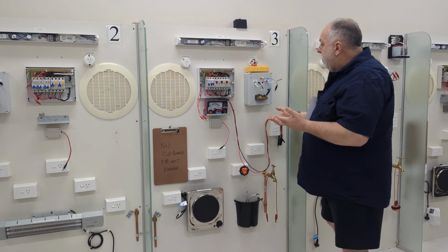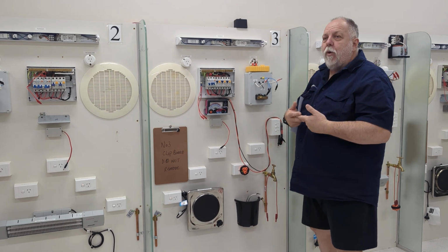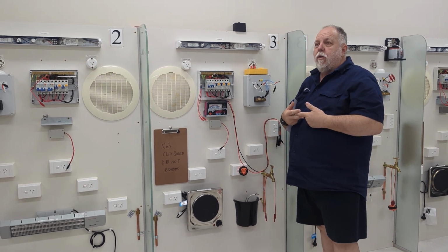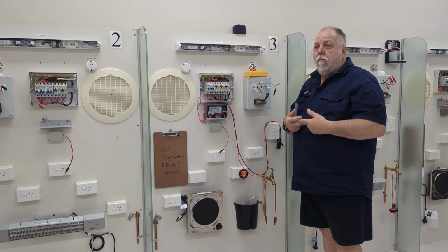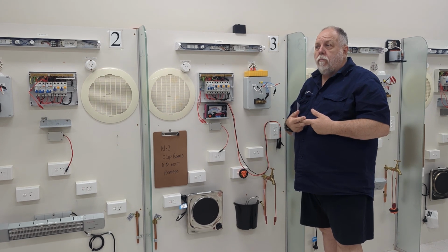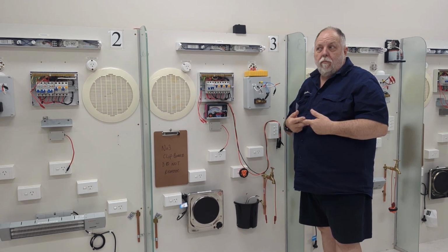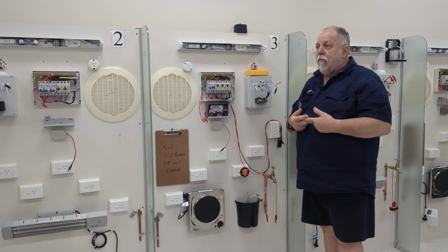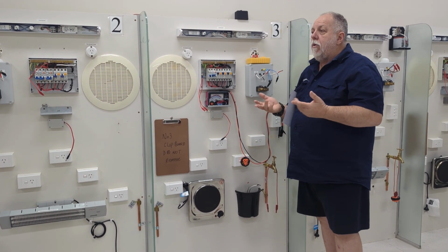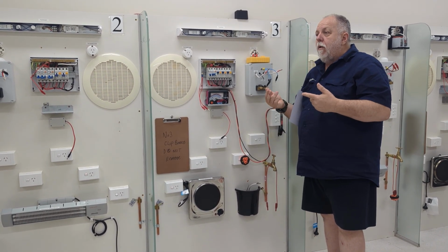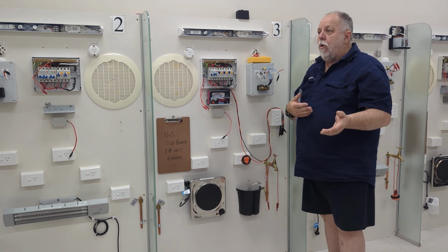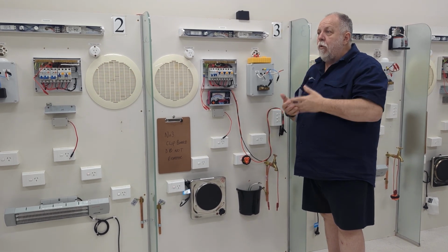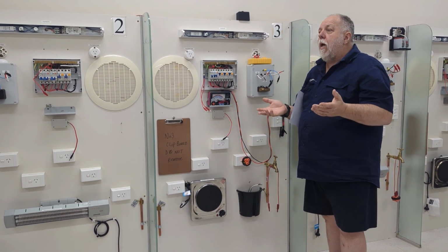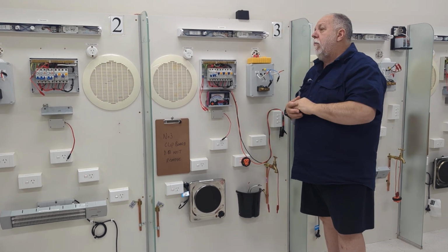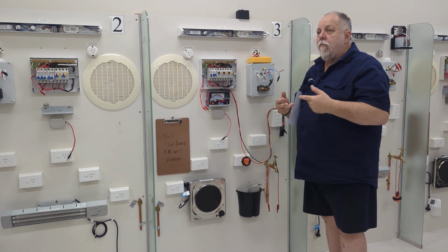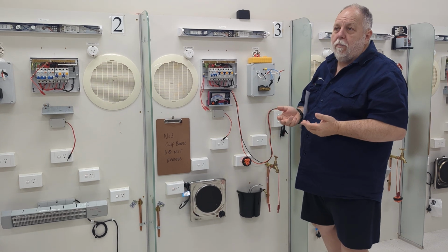Okay? Somebody said to me yesterday, if I had a short between active and neutral on a twin TPS, would that pick it up? Yes or no? Yep. No. Shouldn't it? No, because it's on the same wire. It's on an active wire. Do you understand what I'm getting at? For us to pick up a short, it has to be short to earth. When we do an active and neutral, the only thing something like that would do would create a light to stay on or something like that. So don't forget, on a twin active, if you've got a short on that, it's not necessarily going to pick it up.